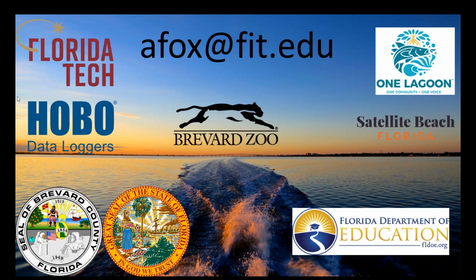Awesome. Thank you so much, Austin. If you have some more on that, go ahead. You mentioned the battery life. For a lot of the other experiments we do, we log every minute, but for our field deployments, we're logging every hour. Their 3 years is based on that 5-minute interval. So we've had really good battery life success. We've had these going for some of them now for 3 years, and we've not had any battery issues.